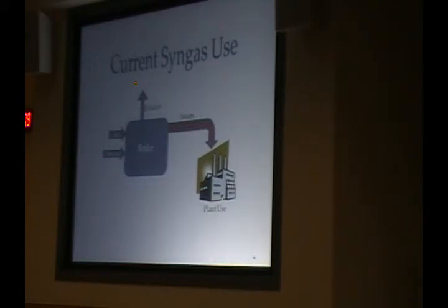Not yet. The problem is there are a lot of pollutants, and there's a lot of spin finish and yarn finish and yarn chemistry in the water, and it really messes up the boilers if you try to send that back to the boiler. So we just flush it down the drain. We do reclaim the heat out of it because it goes out at about 130 or 140 degrees, so we bring in our incoming water and reheat it with the outgoing water.